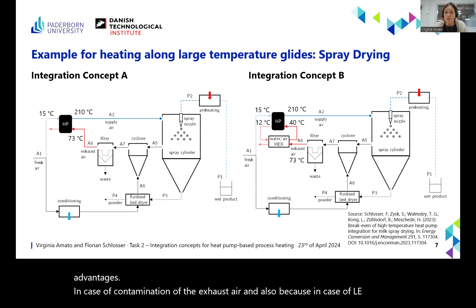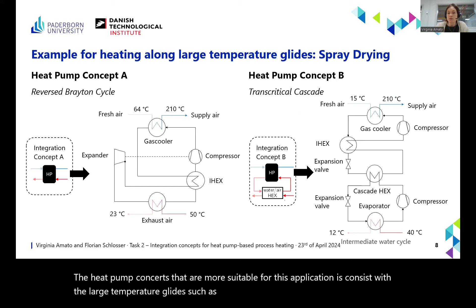Then for this integration concept, there are different heat pump designs that are possible. In general, for drying applications, since air has low heat capacity and density, there are going to be large temperature glides on the sink side. So the heat pump concepts that are more suitable for this application are concepts with large temperature glides, such as Brayton cycles or transcritical cascade cycles.